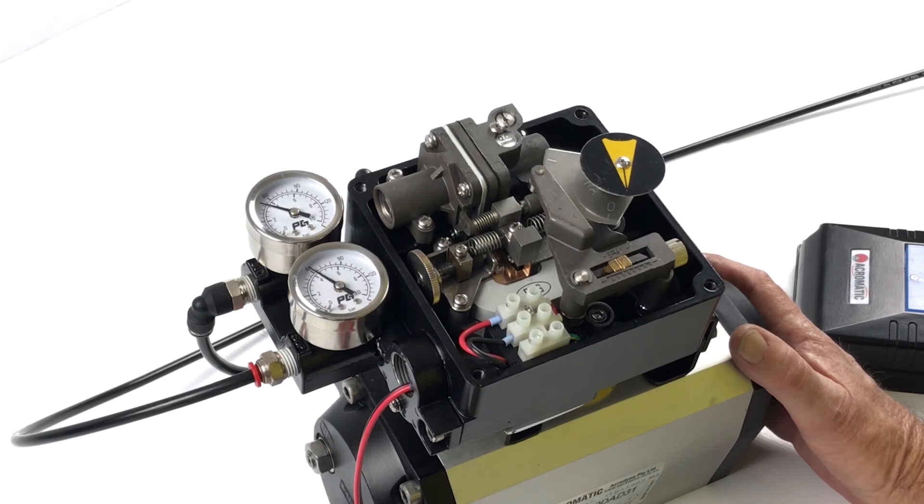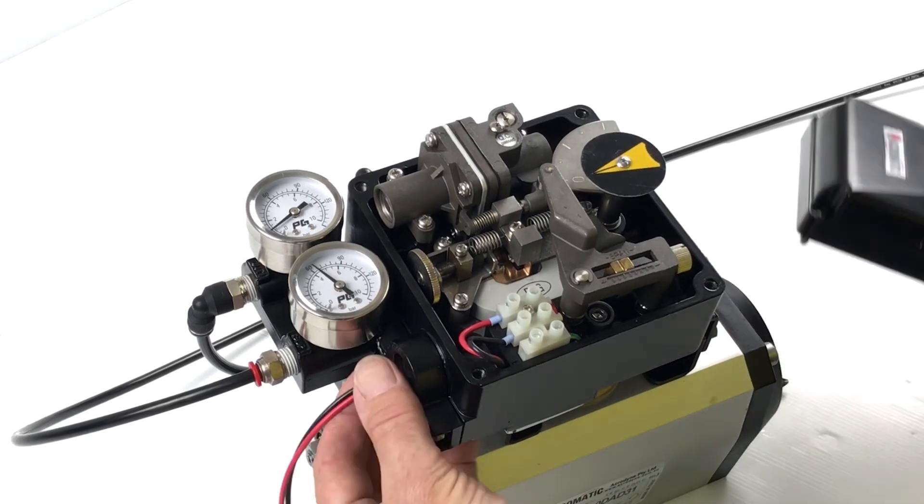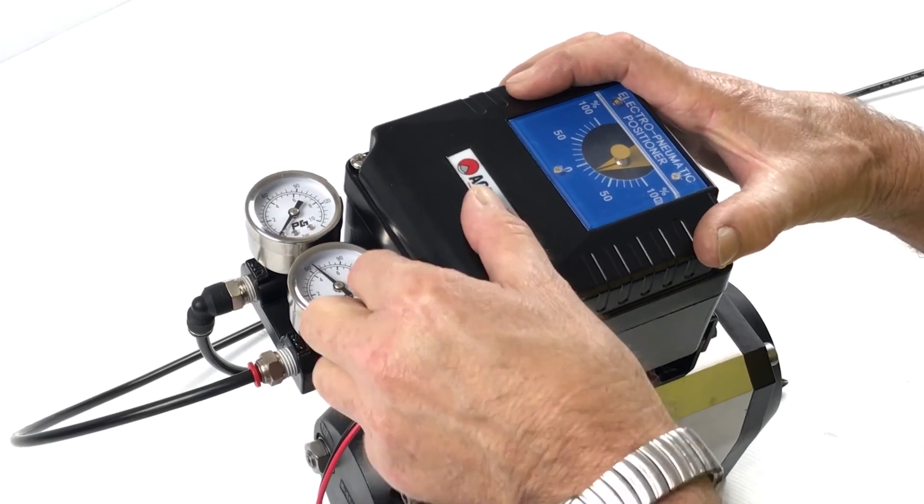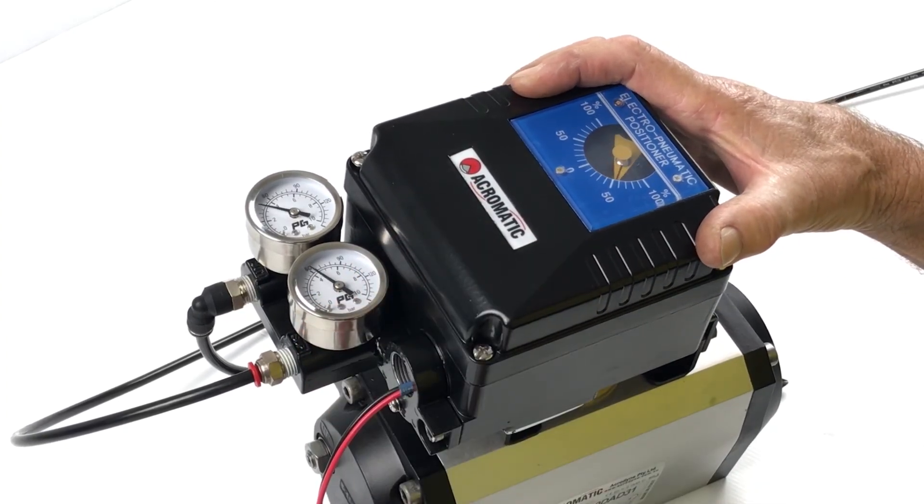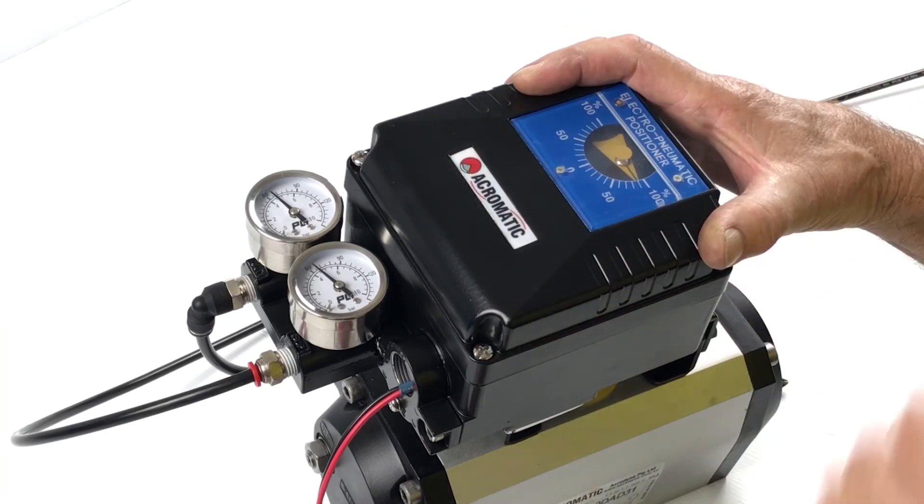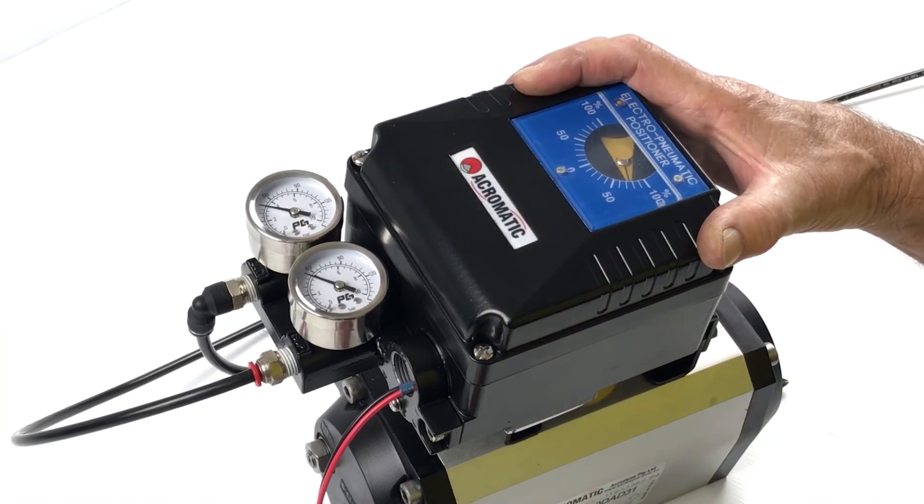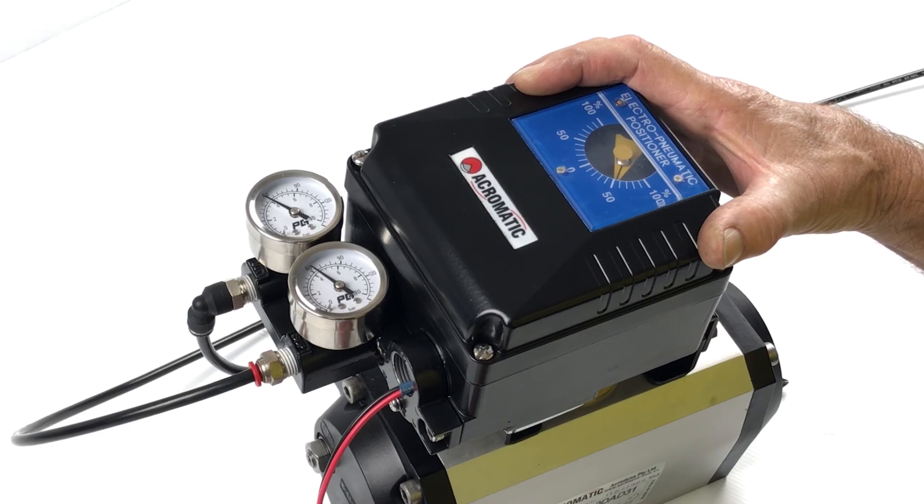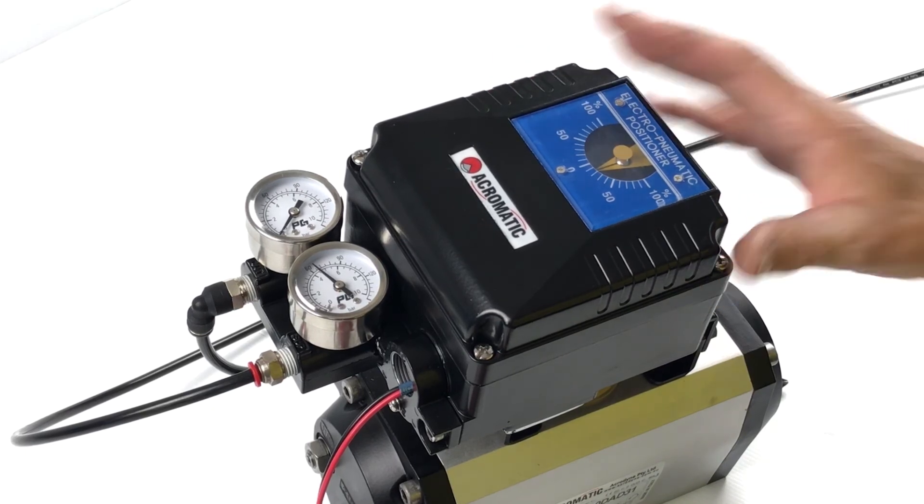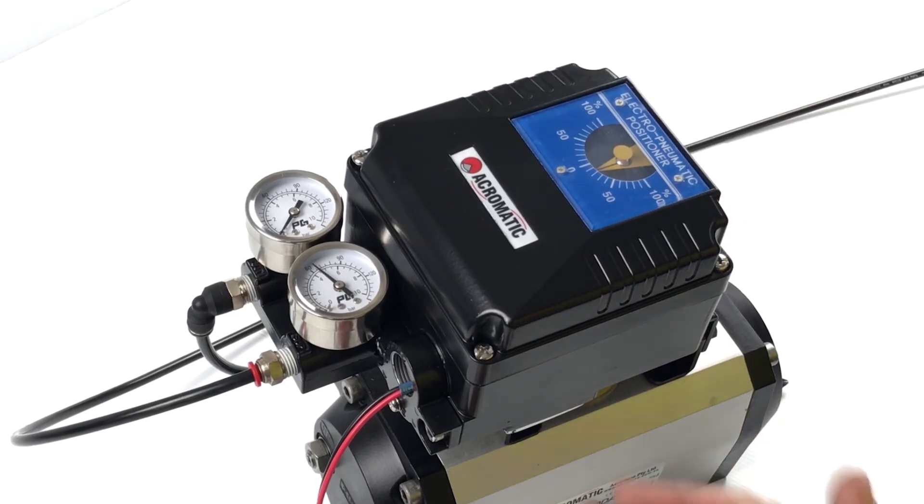Beautiful. It's a case of checking your positions going up and back down also, and complete. That's how you calibrate this positioner.